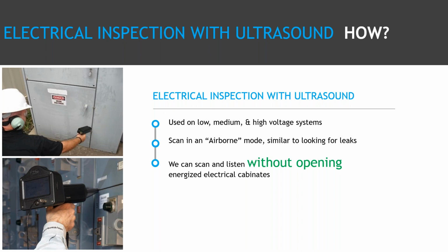The how, again, electrical inspection, any kind of voltage, doesn't really matter, but we're going to use the handheld devices similar to what we would do when we were looking for a leak. So for those of you who have done leak detection as an application, we're scanning, we're looking for the loudest sound, and then once we've found the loudest sound, we're trying to do a sound recording to determine what the problem is. We can scan around those cabinets, any opening, any air gap. We don't have to open any energized electrical cabinets. So from a safety standpoint, that's huge.